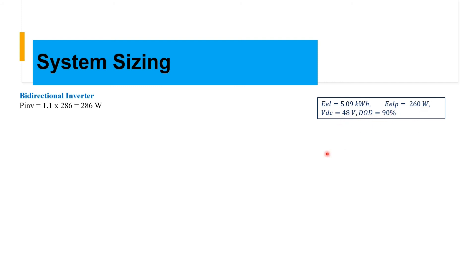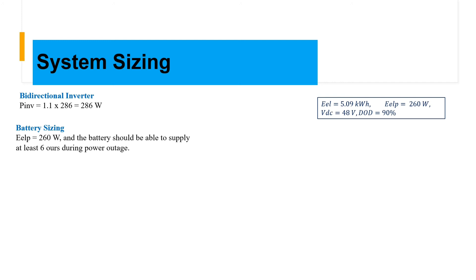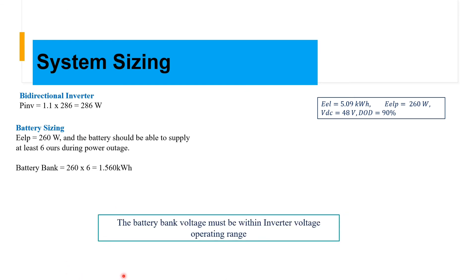We are using a DC system voltage of 48 volts and a depth of discharge of 90%. The battery sizing is based on the essential load power of 260 watts — the battery should be able to supply the load for at least 6 hours during a power outage. Therefore, 260 watts times 6 hours gives us 1.56 kilowatt-hours. You can then go to suppliers and find a battery with this specification, ensuring the battery bank voltage is within the inverter's operating voltage range.